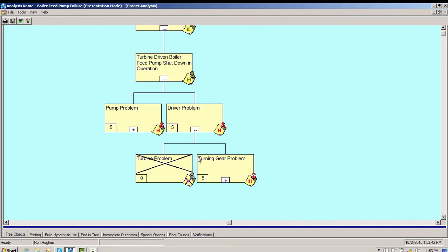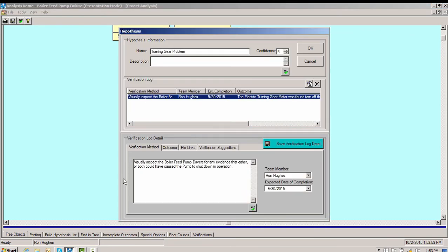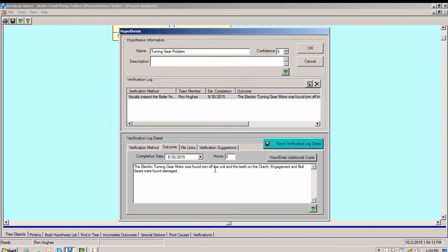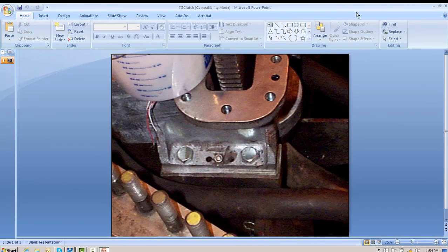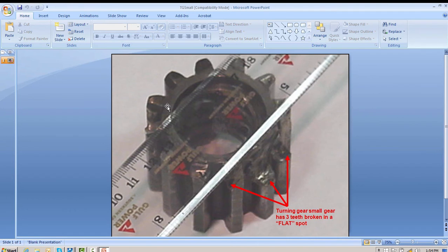Now let's look at the driver problem. How can we have a driver problem? It's either a turbine problem or a turning gear problem. The turning gear problem is evident, but we do inspect the steam chest just to make sure — it's fine. When we inspect the turning gear itself, we visually inspect the Boiler Feed Pump drivers for evidence that either or both caused the pump to shut down in operation. The electric turning gear motor was found torn off the unit, and the teeth on the clutch engagement and bull gears were found damaged. Here's the clutch — you can see it's worn. Looking at the gearbox, you can see where it's been torn off. And the small engagement gear has three teeth missing.